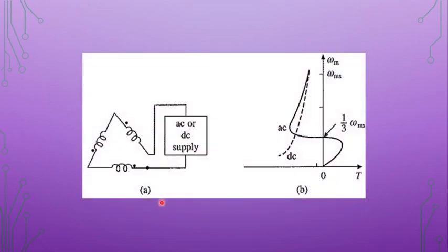Here is the circuit topology of zero sequence braking that can be employed. All the three phases are connected in series. The dot conventions are very important, because we don't want a differential flux effect here. We don't want mutual inductance to interfere and cancel out the fluxes. We want them to be in series, so the dot convention is to be properly followed.